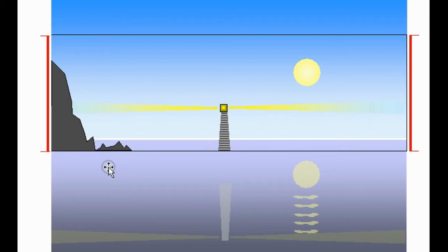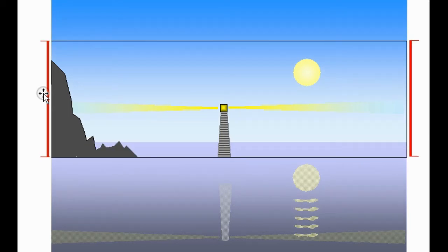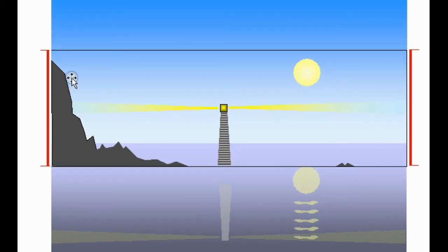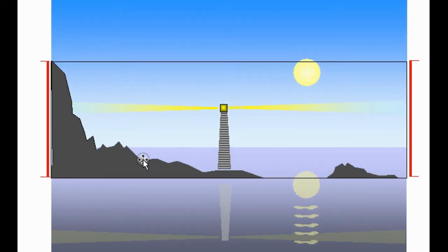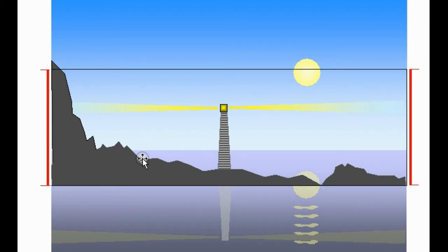So if we go back to our ocean view, here we are with maximum attenuation, and we gradually reduce the attenuation, checking each time that the visible spectrum has not changed. We come to a point where the spectrum may suddenly change. At this point we've gone one step too far, and so what we do is go back one step, and that will be our optimum setting.